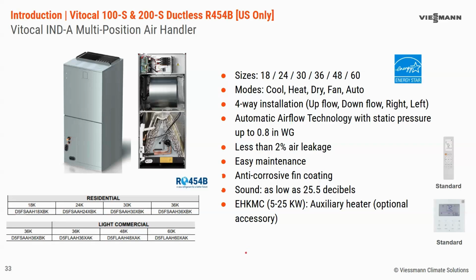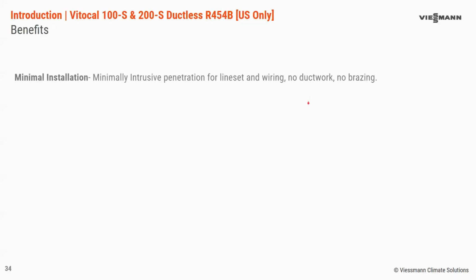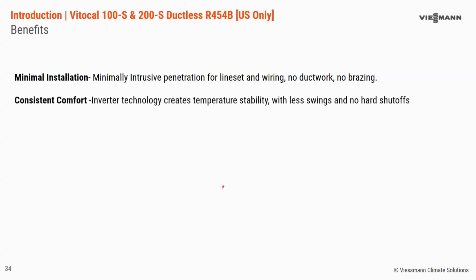For multi-zone, this can be used to give you a hybrid system. So some ducted, some ductless. You are limited in multi-zone to a maximum of 36,000 BTU on the air handler. So the benefits of ductless are the minimally intrusive installation. It's line set and wiring, no ductwork required, no brazing required. You can do flare connections.